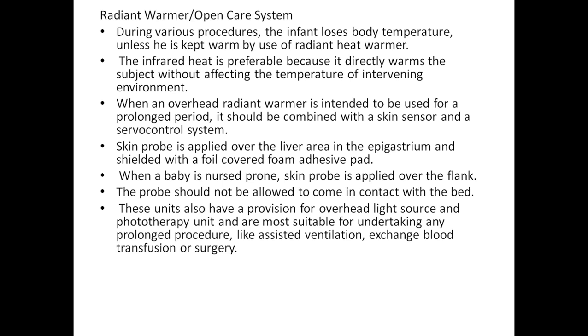The skin probe is applied over the liver area in the epigastrium and shielded with a foil covered foam adhesive pad. When the baby is nursed prone, the skin probe is applied over the flank. The probe should not be allowed to come in contact with the bed.